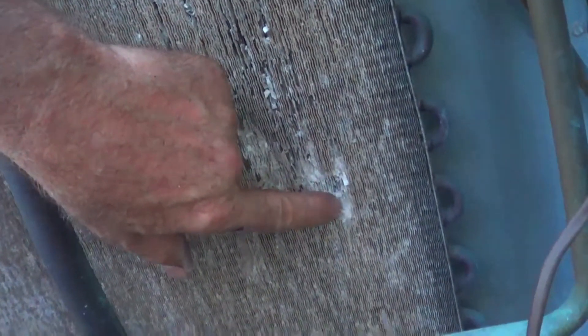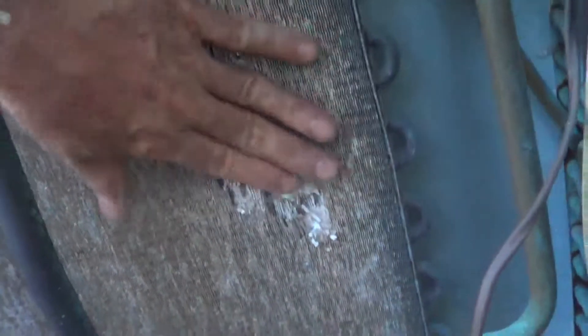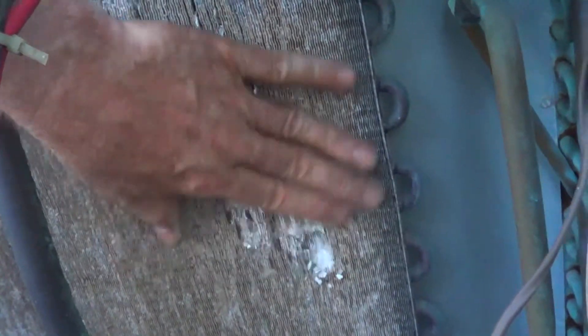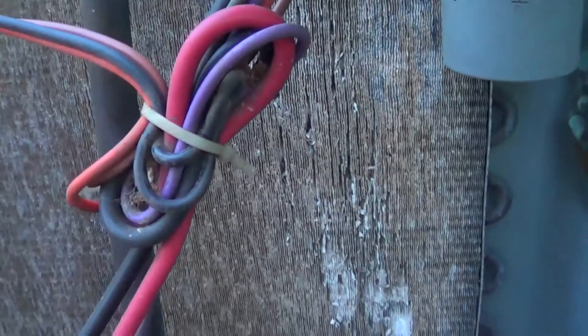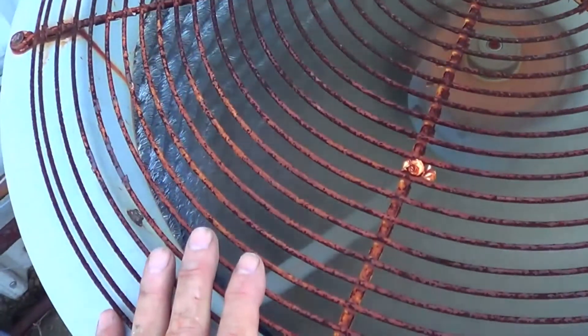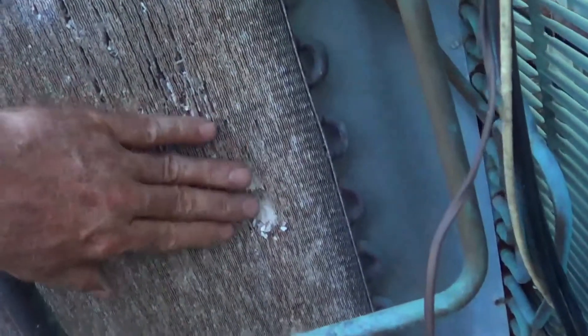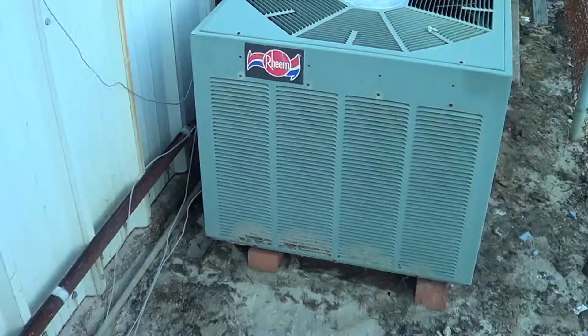Look at this — this is due to the salt air here. Touch it, it just crumbles. This might be kind of a basket case. That's a Rheem, it's about 20 years old. The Carrier over here — the Carrier around the coils are actually still good. This one's actually 10 years newer and it's got crappier coils. This is salt air here.